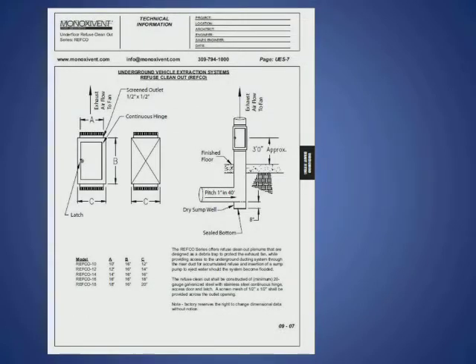This is a typical application where you see the ductwork is pitched to one spot, and this is where the ductwork would exit. We strongly recommend this type of sump built into the bottom of our riser that you see on the left. This allows you, if there were a flood, to throw a pump in there and pump it out. Or in the case of a wash down, sometimes they wash the salt down from the floors and it all ends up in there and you can pump it out. And the Monoxivent refuse clean out unit, which is again a catalog item, can sit right on top of that and allow you to get in there.